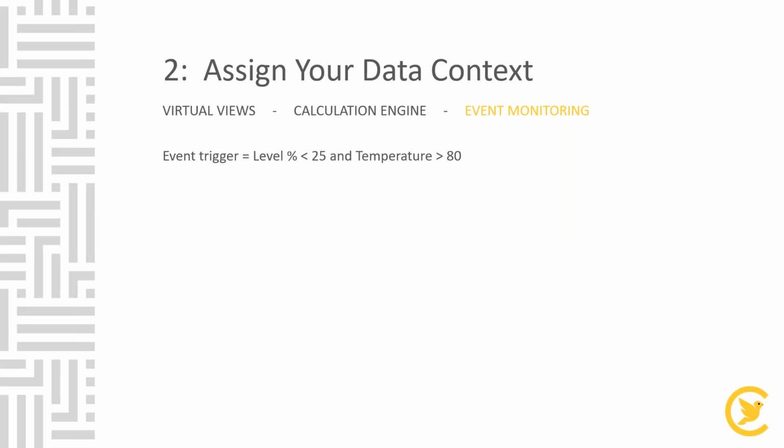So this is about, if I want to set a condition for the reporting, can I have something to understand from level percentage of 25, and then the temperature more than 80? So how do you trigger a particular event? You can do a lot of if, or, and, so that you can trigger and then send a report based on that to a particular person concerned. Particularly, I would say, when there are risk concerns. So if the PI is above 100, you need to notify who, or maybe some immediate action needs to be taken to make sure the pressure runs back into a normal environment.